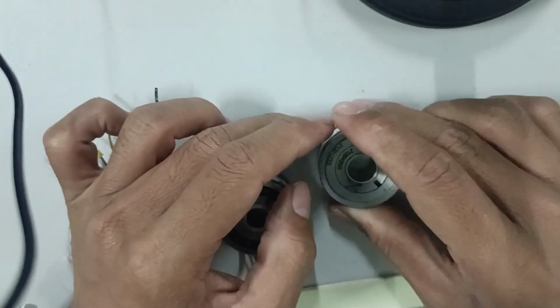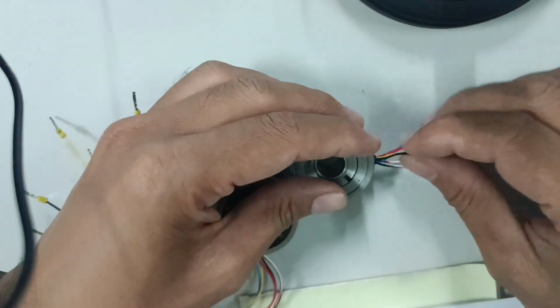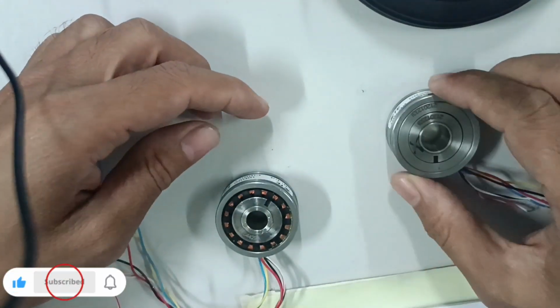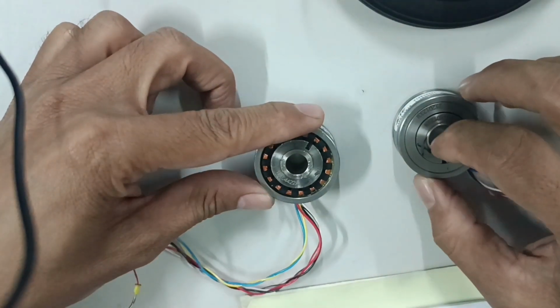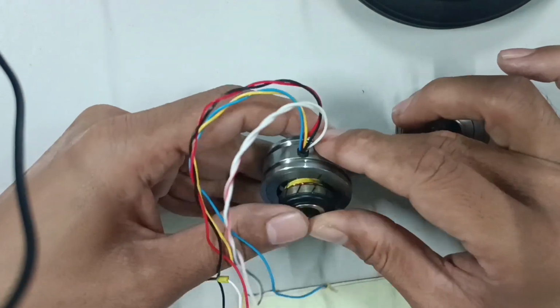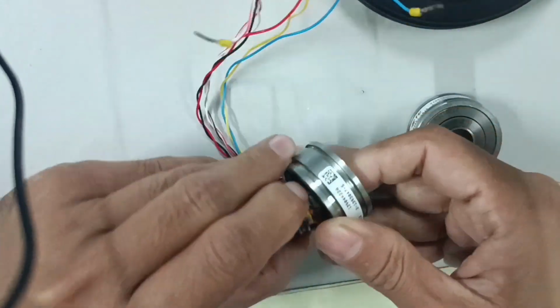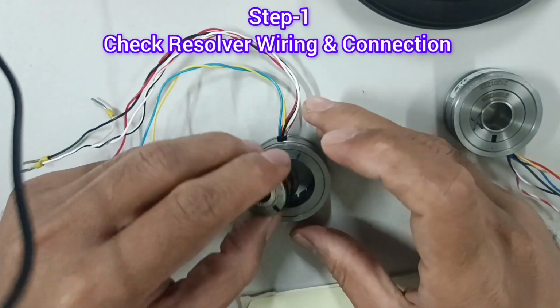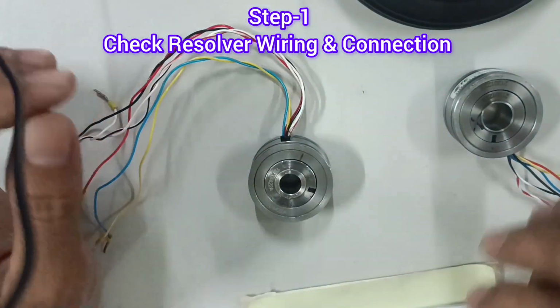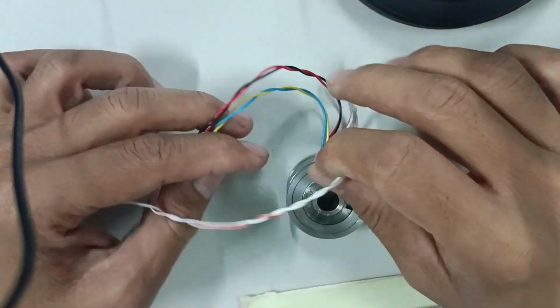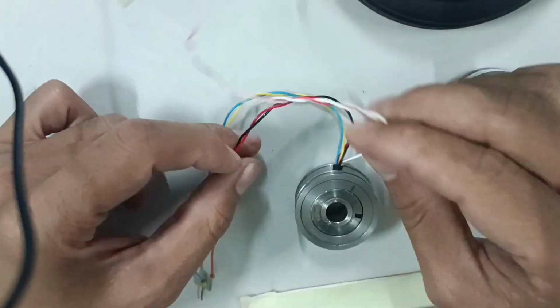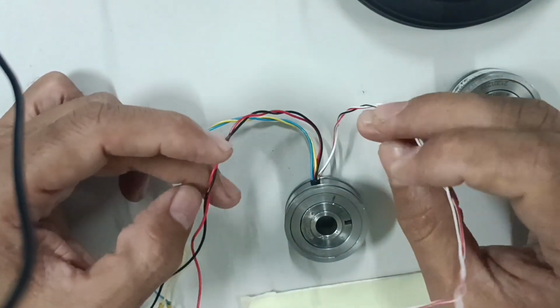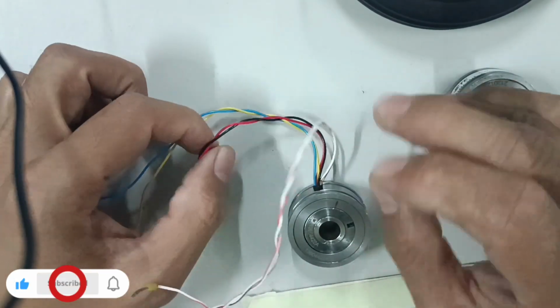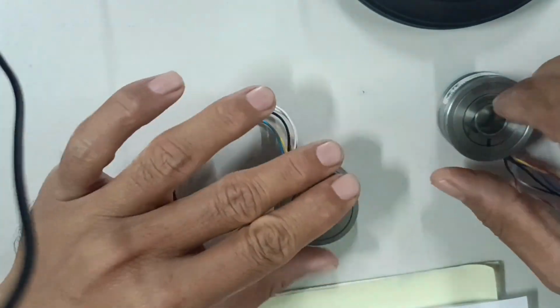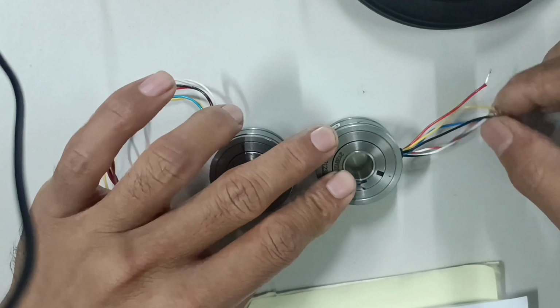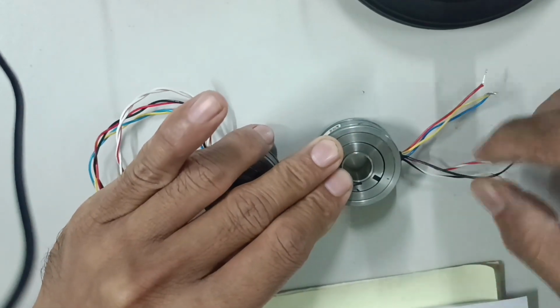I have mentioned here six steps for the complete solution for the resolver. You can follow step 1 to 6 step by step. Step 1: check resolver wiring and connections first of all. Verify that the resolver cables are securely connected to the servo drive or controller. Inspect for damaged or cut cables. Use a multimeter to check the continuity in the resolver cables.